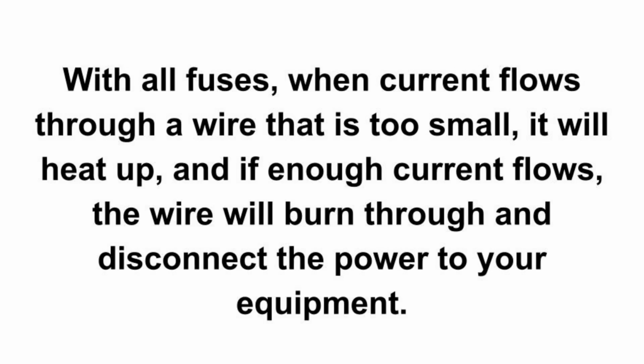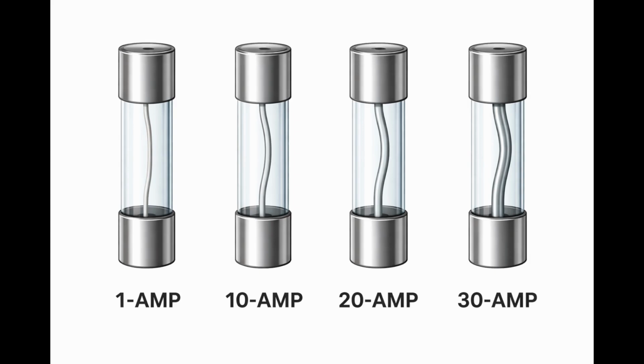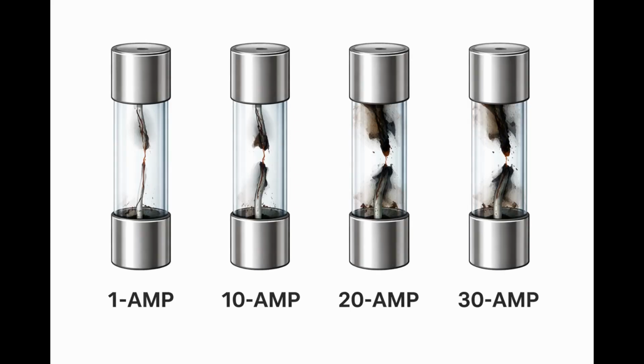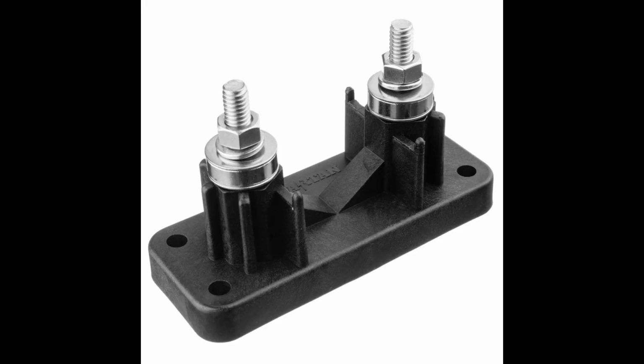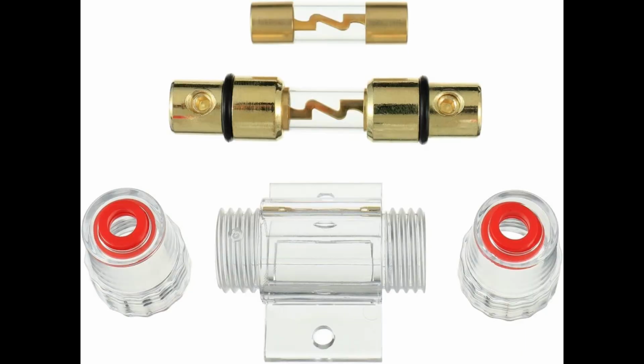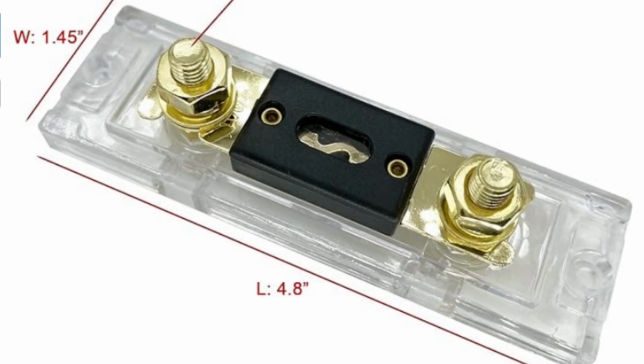With all fuses, when current flows through a wire that is too small, it will heat up, and if enough current flows, the wire will burn through and disconnect the power to your equipment. This diagram shows the different sizes of wire inside a fuse. The higher amperage that a fuse can handle, the larger the size of the wire will be. Here is what a blown fuse would look like. Here are a few examples of other styles of inline DC fuses you could use on your system.